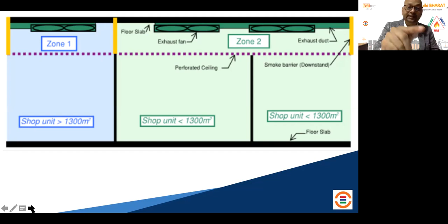First and foremost, what is important, I can tell you, is that you need to make these zones according to your occupancy. Your zone classification must follow the codes and compliances. There are building occupancies which are defined in NBC. If this occupancy is mercantile, then there is a certain cap given by the code, that it should not be more than 1300 or 1100. So when that input comes to you from NBC that this is your limit, then it is important for you to play on those limits by using smoke barriers, or by creating fire curtains, or by creating walls which are 2-hour rated.